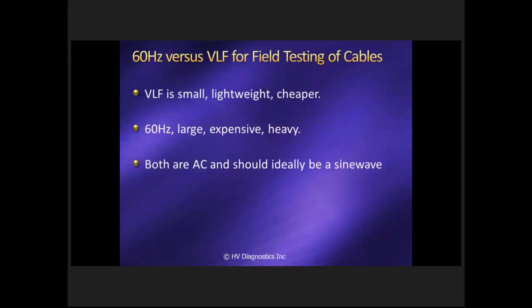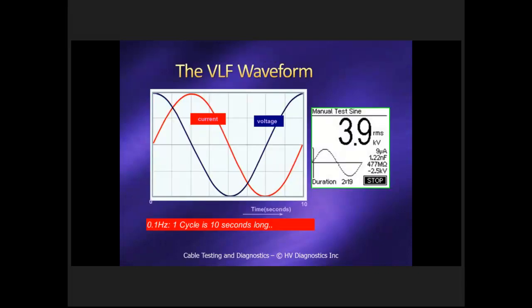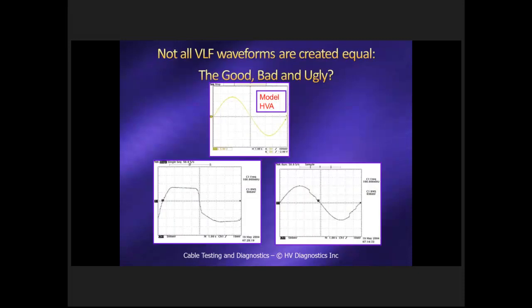So 60 hertz versus VLF: obviously VLF is much smaller because the power requirements are smaller, so it's lighter and cheaper. 60 hertz is larger and more expensive. Both are AC, however, and both should be a sine wave. They should not be any other type of waveform. The DC hipot has obviously been replaced by an AC hipot, not only for the purposes of withstand testing the cable, but for partial discharge or offline testing as well. The VLF waveform is 10 seconds long, as you can see by that waveform over there. Because we have a capacitive load, you can see a current-voltage phase relationship of about 90 degrees. And you can get various parameters from the VLF, such as current, capacitance, etc.